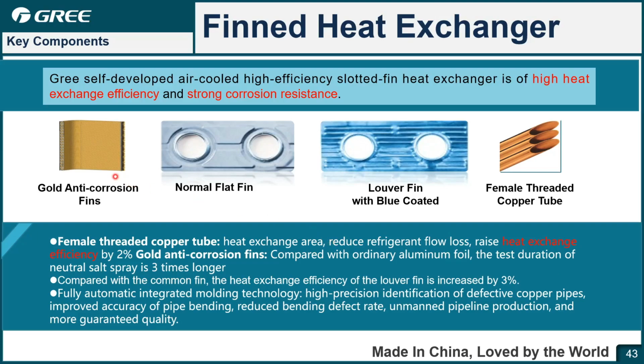Next one is the heat exchanger. For auto units, we take some anti-corrosive treatment, such as the painting. We use the golden painting for the protection, and also the fin. You know, for the normal flat fin, the heat exchanger efficiency may be not very high. However, the VERSATI 3 use this one, the louver fin with blue coated. So you can see there are some slits. Yeah, also with the coating. This fin, the heat exchange efficiency is higher. For the copper pipe, it's the female threaded pipe, also better for the heat exchange. So in general, the heat exchanger, we take the anti-corrosive treatment and also the fin and copper tube to make sure the heat exchange can be improved.